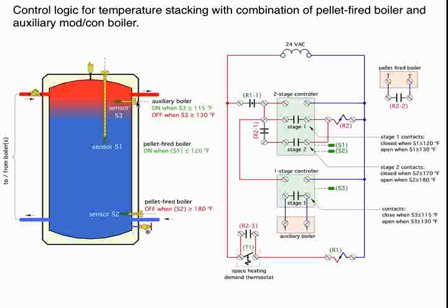If you want to combine it with an auxiliary boiler, we can put another sensor up near the top. And notice we're only firing the auxiliary boiler once our tank is almost depleted of hot water. We're trying to hold off on the firing of that boiler as long as possible, especially if the pellet boiler is starting to put heat back into the tank again. So we could set up some condition, which we'll call a last resort condition, where we do go ahead and fire the auxiliary boiler. In this case, I'm going to wait until this upper tank sensor drops down to 115. This is assuming the load, by the way, needs 120 degree water. So I've cheated a little bit. I put a 5 degree differential in there. And then we're going to keep that auxiliary boiler going until that upper sensor gets to 130. And all that requires is the addition of one more single stage set point control to our control logic here.